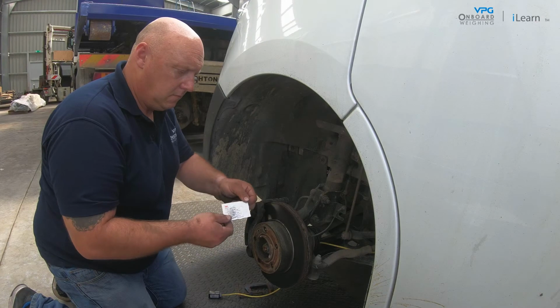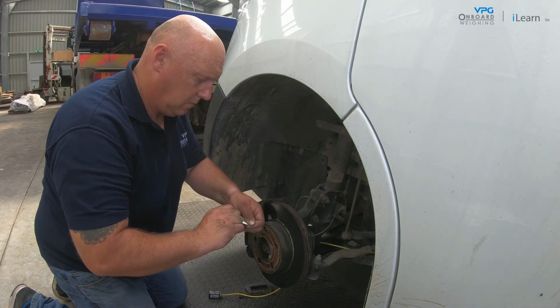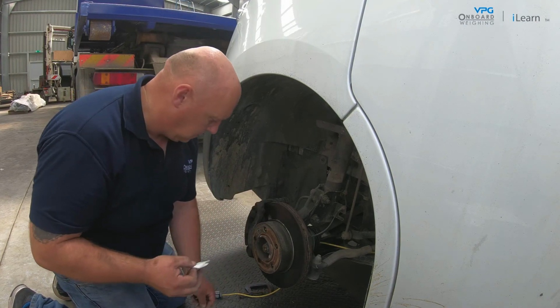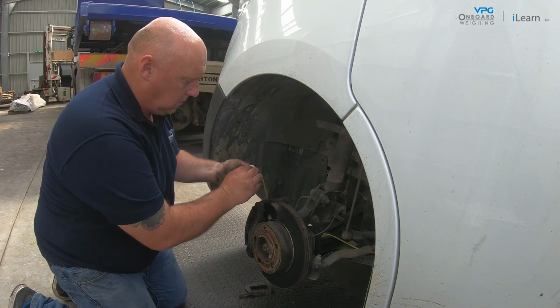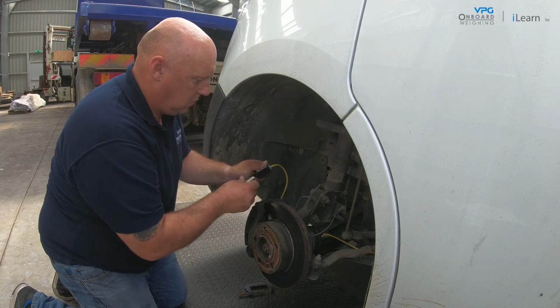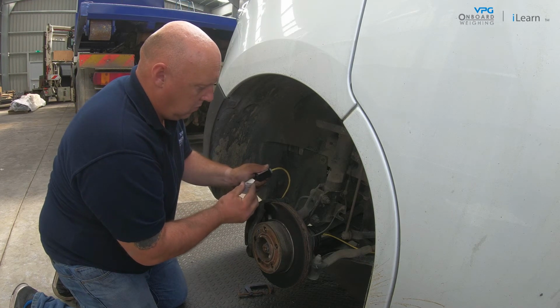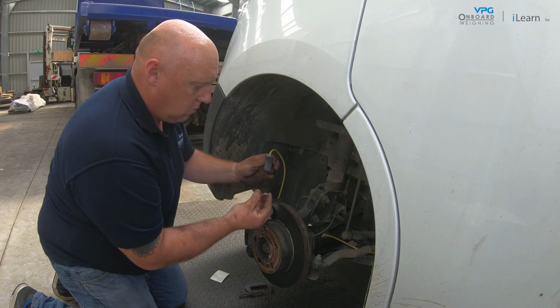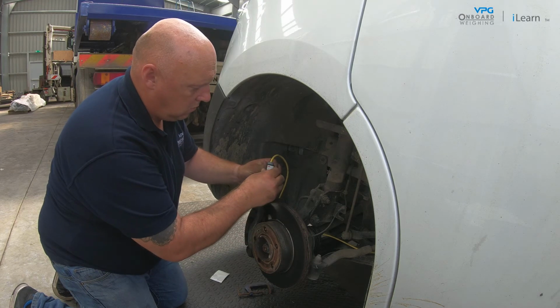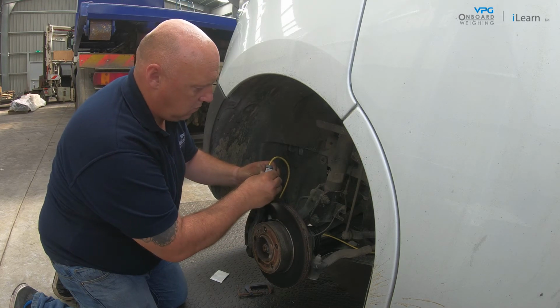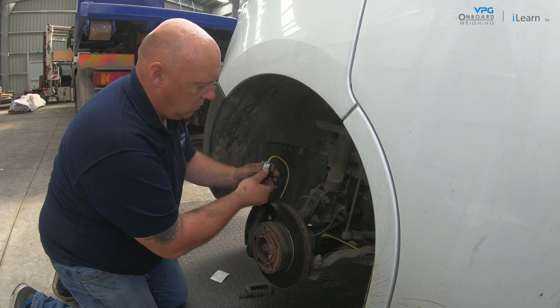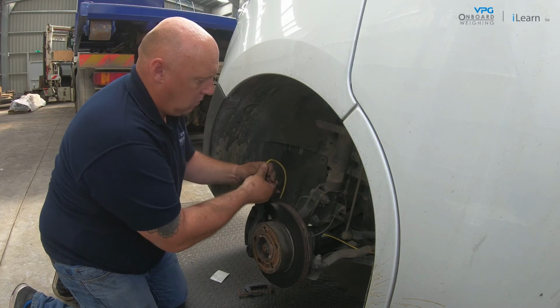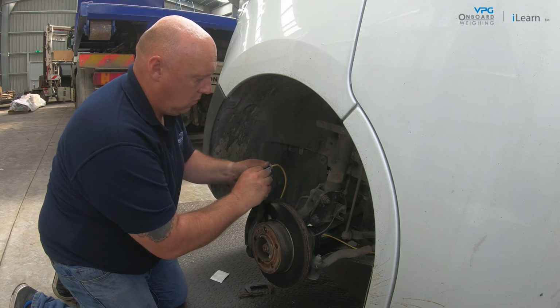Next, use the alcohol wipes to clean the mounting surface of the transducer. Once dry, apply the VHB bonding tape. The ideal temperature to help the tape to bond to the metal surface is 15 degrees centigrade, 60 degrees Fahrenheit. If necessary, use a heat gun to heat the spring before mounting the transducer.